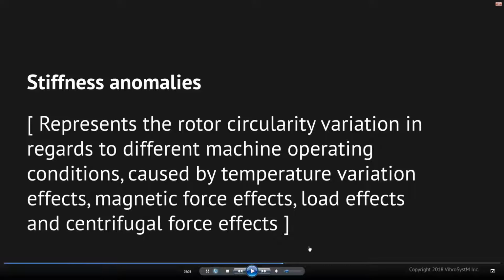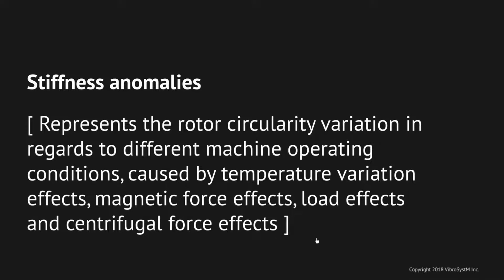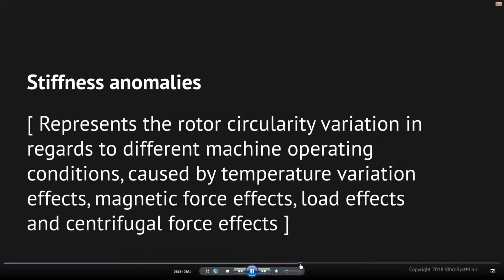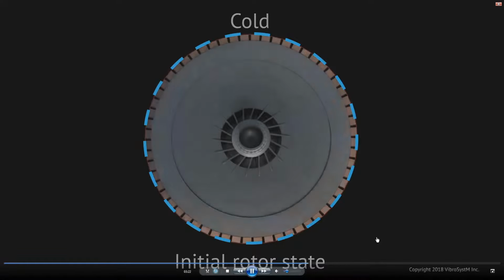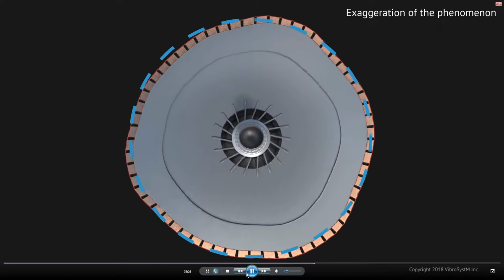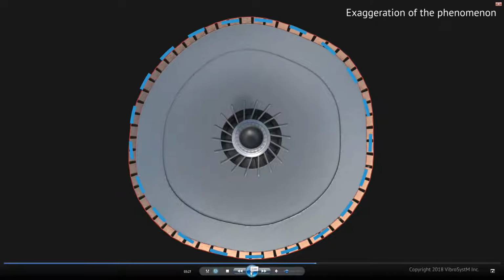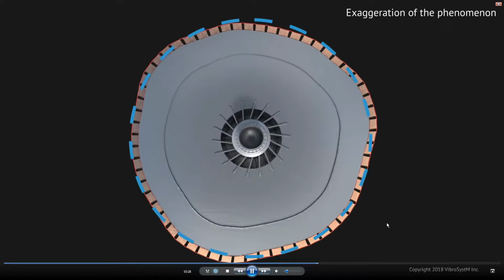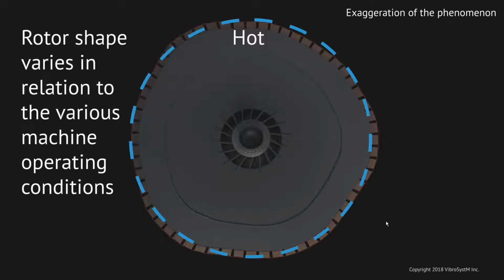Now the stiffness anomaly analysis, it represents the rotor circularity variation in regards to different machine operating conditions caused by the temperature variation effects, the magnetic force effects, load effects, and centrifugal force effects. So again, we look at distortions, but contrary to the circularity issue, circularity is basically looking at the same condition through time and see if that circularity changed. For example, if you look at the circularity at full load hot in January, what does it look like in April? What does it look like in July? Whereas the stiffness, we're looking at how does the rotor change or perform going through all the different conditions from cold all the way to full load hot. And again, in some cases, we can spot some significant distortions that need to be addressed.